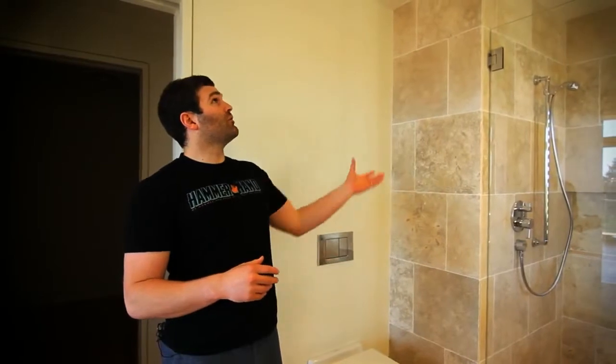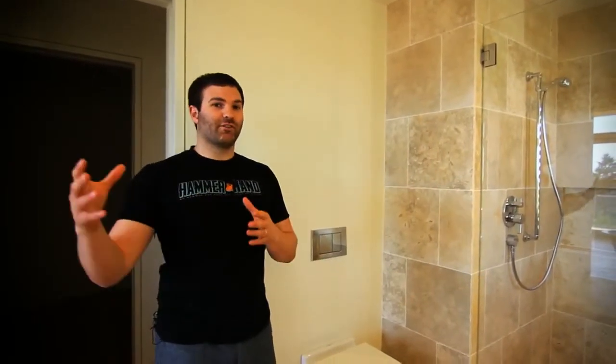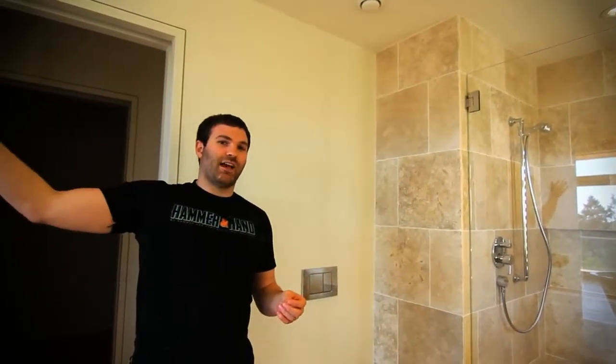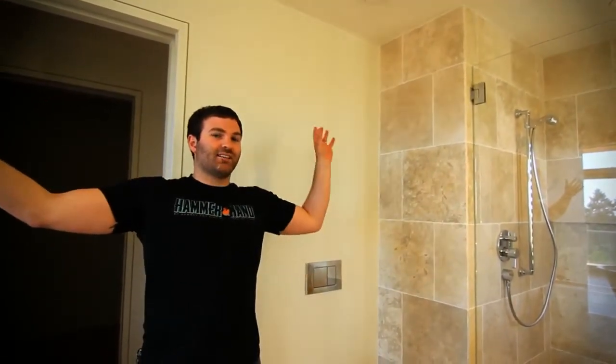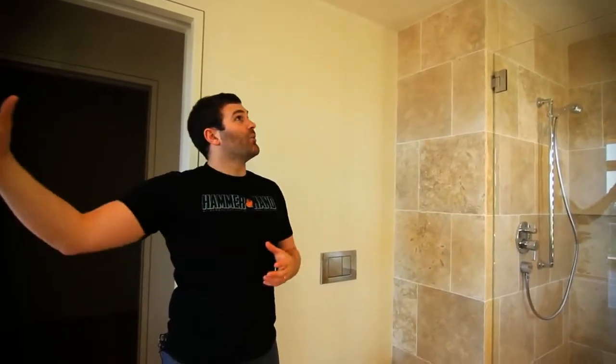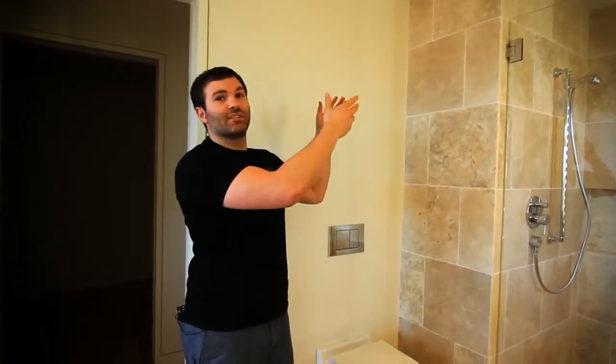In the bathroom, where we're generating moisture, odors, and also in the kitchen, we're pulling air out in a balanced fashion. For every cubic foot of air that goes out, a cubic foot of fresh filtered outside air — tempered by the energy from this outgoing air — comes in through the bedrooms, washes through the house, and goes up this exhaust. The great thing is we're getting constant mixing of fresh air and really low pollutant particulate counts because of that constant background air exchange.